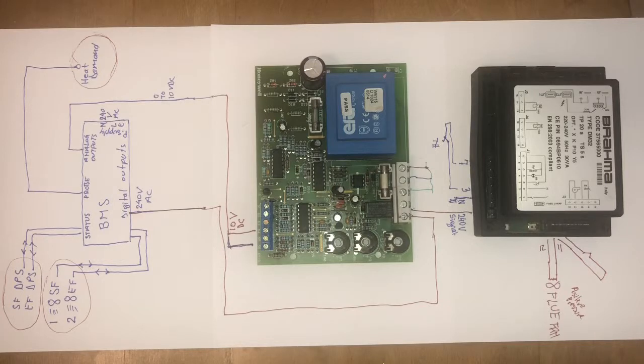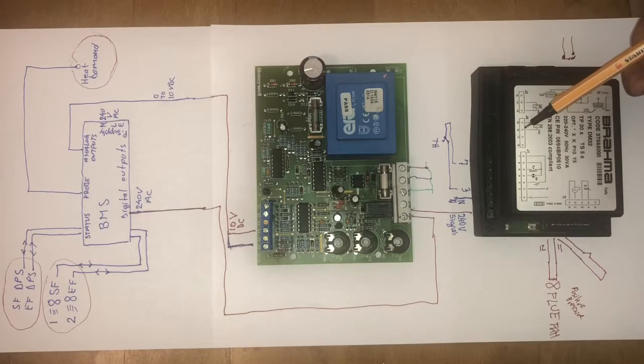Then after that, the Brahma controller will start igniting the system. So it will ignite the system, and when it does, it will spark here, make like a zip, like a spark in between the spark plug and the earth, and there will be a little blue flame, and when it's got the little blue flame, the valves VG1 and VG2 will open, so you'll have a power supply at 14, 13, 18 and 19. You'll have the power supply and these two valves will open.